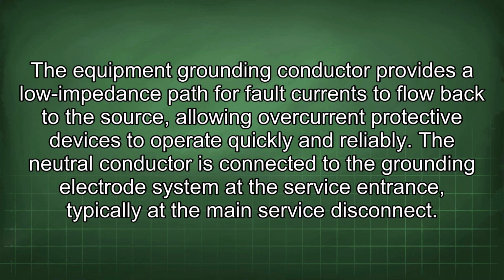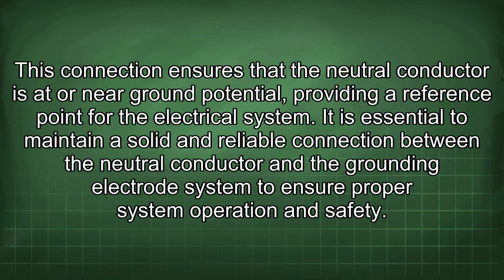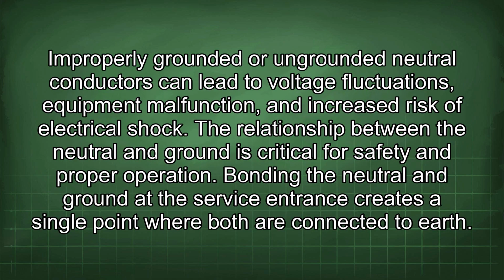The neutral conductor is connected to the grounding electrode system at the service entrance, typically at the main service disconnect. This connection ensures that the neutral conductor is at or near ground potential, providing a reference point for the electrical system. It is essential to maintain a solid and reliable connection between the neutral conductor and the grounding electrode system to ensure proper system operation and safety. Improperly grounded or ungrounded neutral conductors can lead to voltage fluctuations, equipment malfunction, and increased risk of electrical shock.